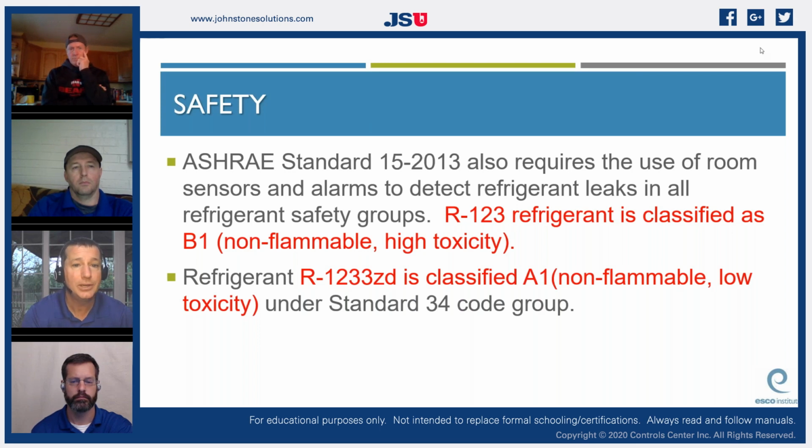So ASHRAE standard 15 of 2013 also requires the use of a room sensor and alarms to detect refrigerant leaks in all refrigerant safety groups. So anytime we have a big machinery room, no matter what refrigerant it is, we're going to have some kind of leak detection.